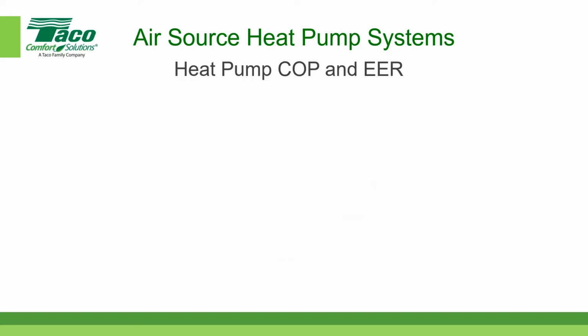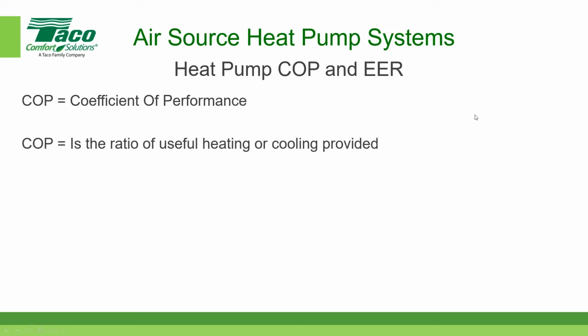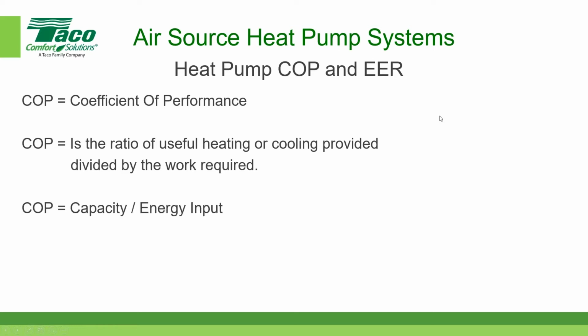So let's start talking a little bit about COP and EER. COP stands for the coefficient of performance, and by definition, it is the ratio of useful heating or cooling provided divided by the work required. It's in the same units. In other words, it's the capacity divided by the energy input.